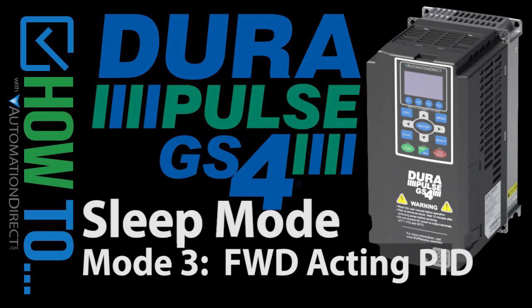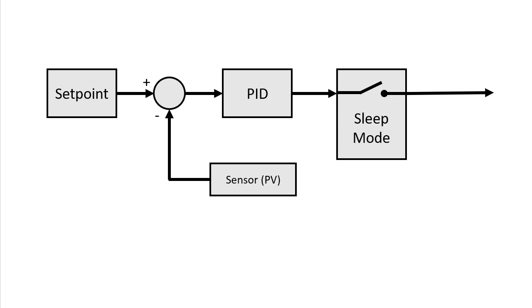In this video we'll use the GS4 sleep mode 3 with a forward acting PID loop that controls the motor by watching the sensor feedback signal or process variable to decide when to turn the motor on and off.